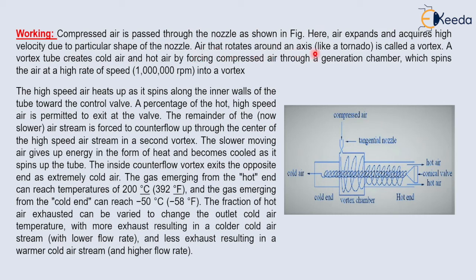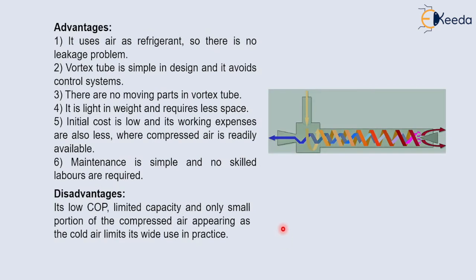The advantages of vortex tube refrigeration are: it uses air as refrigerant so there is no leakage problem; it is simple in design and avoids complex control systems; there are no moving parts so maintenance issues are minimal; it is light in weight and requires less space; initial cost is low and working expenses are also less where compressed air is readily available; maintenance is simple and no skilled labor is required.